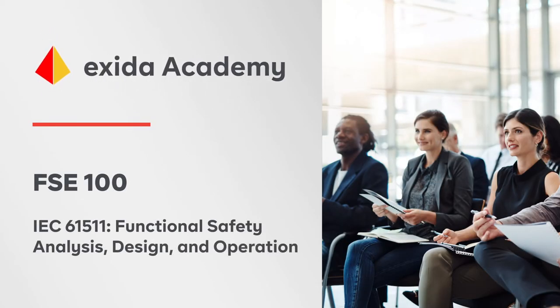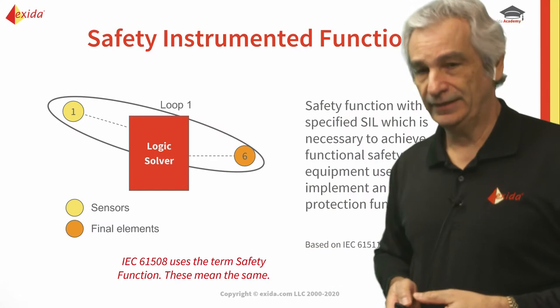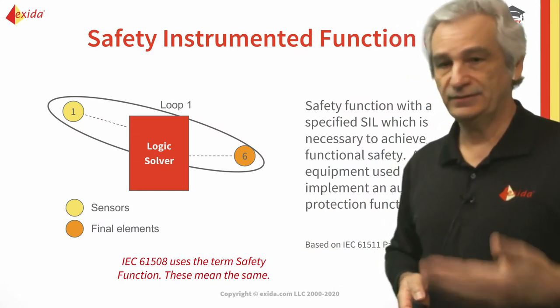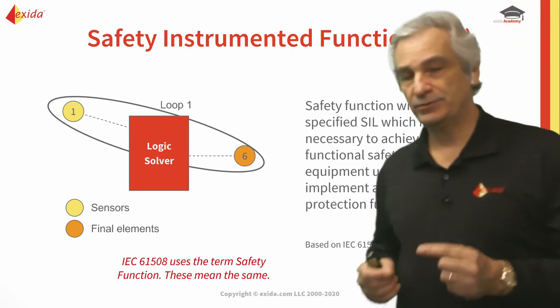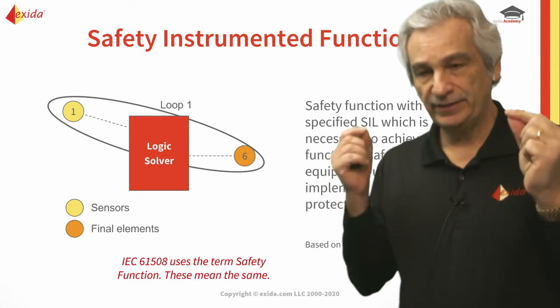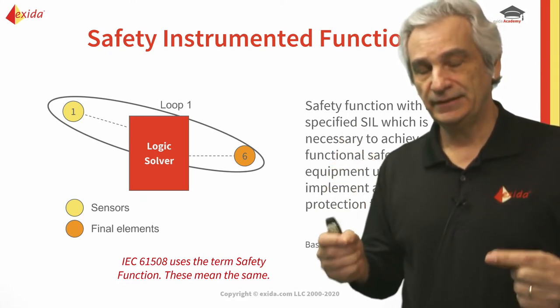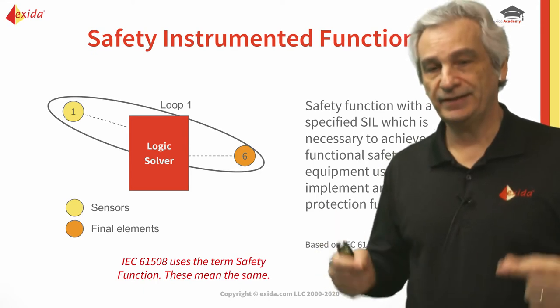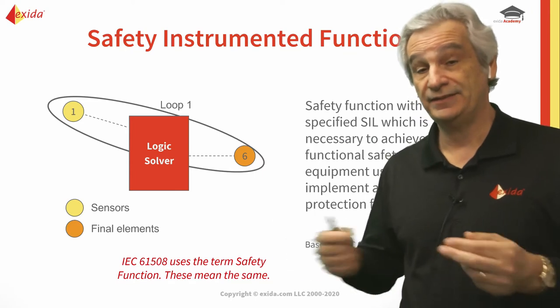If we look at the safety instrumented function again, this will act automatically to bring the process to the safe state. So it's a protection function and it will use sensors, logic solver, and final element. With safety instrumented functions, it's a one-for-one — dealing with a single specific hazard and acting automatically to bring that process to a safe state to prevent that hazard.